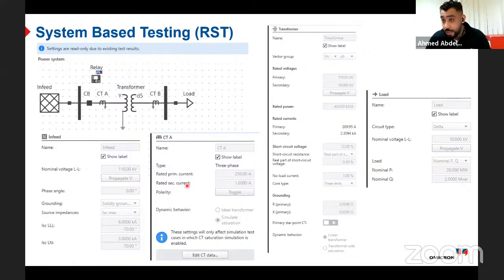The CT, because you tested the CT on site with our product, for example a CT analyzer, then you can get the CT characteristic and results from the CT analyzer, edit the CT data, then import it to RelaySimTest, and you will have the real values from the CT, which is installed on your transformer, not from the data sheet, not from the factory acceptance test report. You can get it as an XML file from the testing equipment where you tested the CT. Then you can define the transformer: the number of windings, the short circuit voltage, the percentage impedance, the core type, the no-load current, the grounding of the transformer, whether it is grounded or not, the full detail of a transformer.